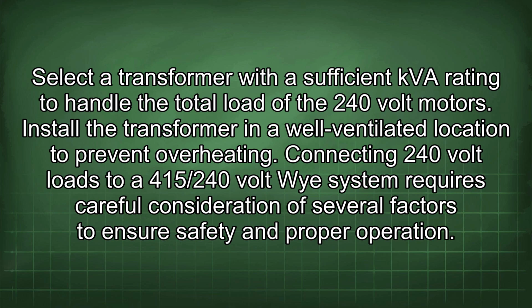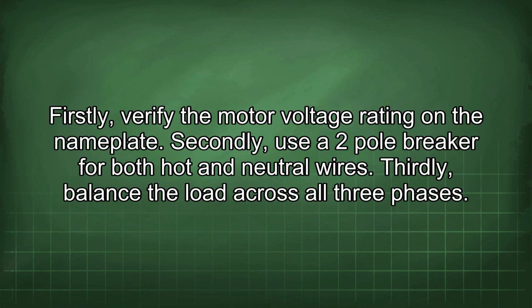Connecting 240-volt loads to a 415/240-volt Y system requires careful consideration of several factors to ensure safety and proper operation. Firstly, verify the motor voltage rating on the nameplate. Secondly, use a 2-pole breaker for both hot and neutral wires. Thirdly, balance the load across all 3 phases.